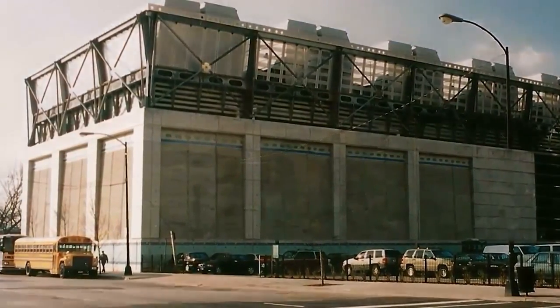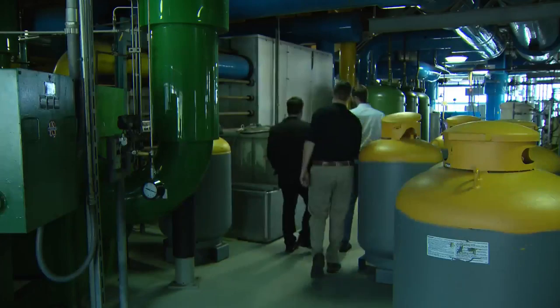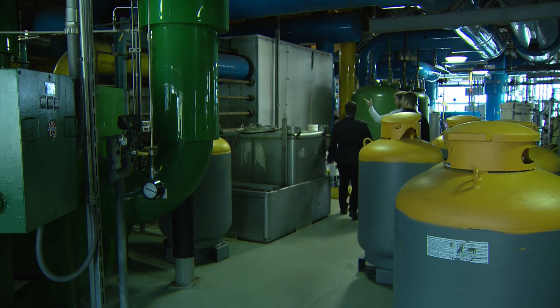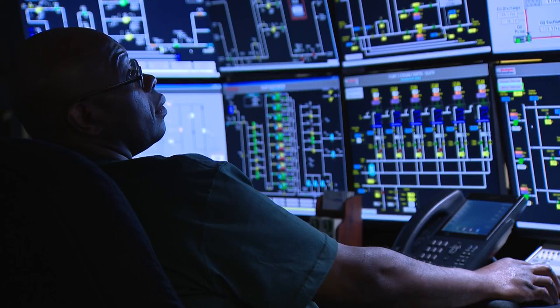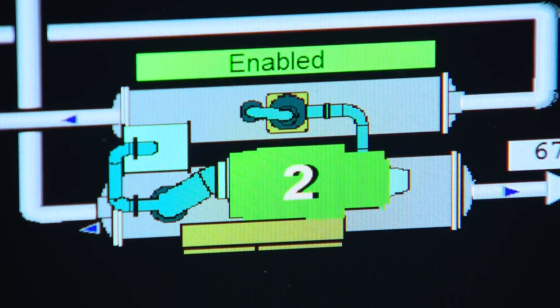Here at Plant Number Two, behind these walls, is a massive storage tank — a water cooler measuring more than 100 feet long, 90 feet wide, and 30 feet high. The tank holds what could be called an industrial-sized ice maker: 435 miles of tubing and 434 cooling coils, some large heat exchangers where refrigerant chills the water. We have machines called chillers that can chill the water or produce super-cold glycol — like antifreeze — which is pumped through tubes submerged in a water tank, and on those tubes ice forms.